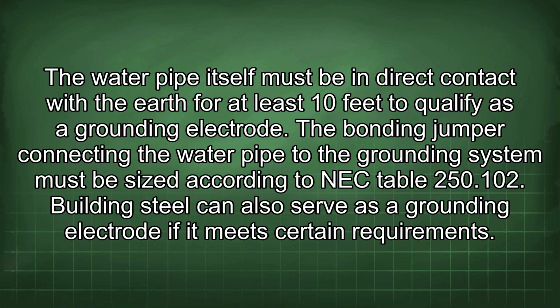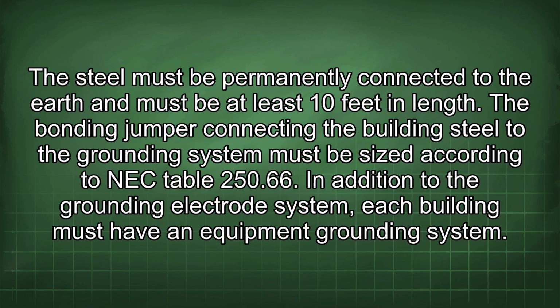a grounding electrode. The bonding jumper connecting the water pipe to the grounding system must be sized according to NEC Table 250.102. Building steel can also serve as a grounding electrode if it meets certain requirements. The steel must be permanently connected to the earth and must be at least 10 feet in length. The bonding jumper connecting the building steel to the grounding system must be sized according to NEC Table 250.66.